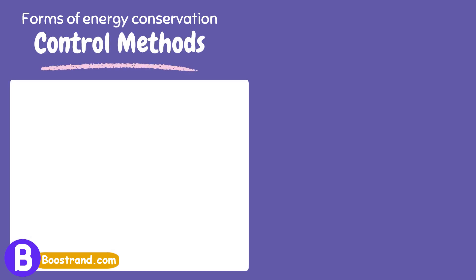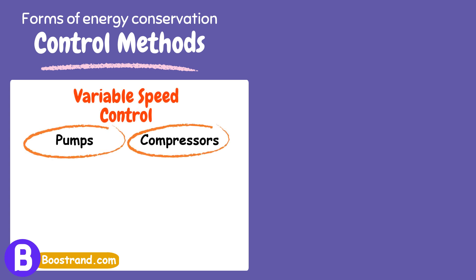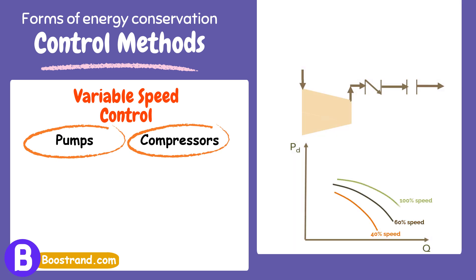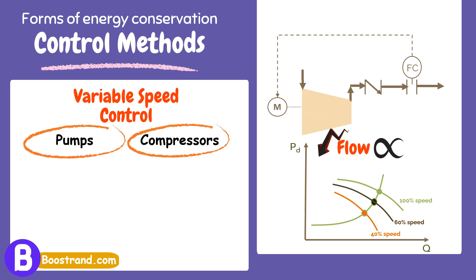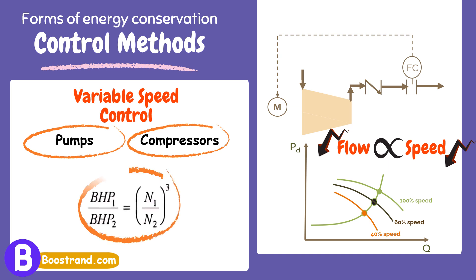The fifth way is control methods, which can significantly save a lot of power. A famous example is the use of variable speed drives in pumps and compressors. Variable speed drives (VSD) allow the speed of pumps and compressors to be adjusted to match the process demand. This is much more energy efficient than running them at constant speed and throttling the flow with control valves. When we need much less flow from the pump or compressor, we can reduce the speed of the impeller instead of throttling the discharge control valve. This shall dramatically reduce the power consumed, as power is proportional to the cube of speed.